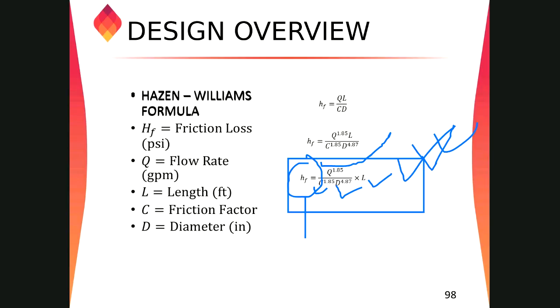Yes, we already discussed all of this, and the software do all of this, and also calculate the fittings and the equivalent length. We have to put the number of fittings between the nodes, then they will calculate. If you are not putting the fittings, then they are not going to calculate that one. Exactly, we have to make sure of that. We'll discuss that in the design course.